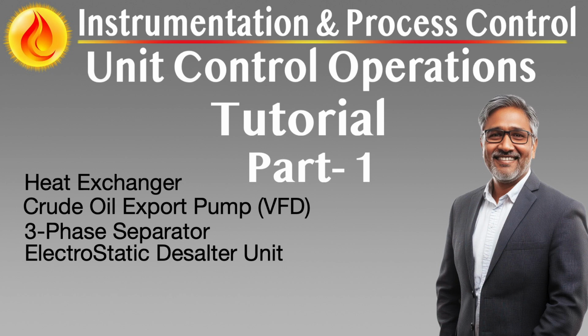From a safety and reliability standpoint, electrostatic field protection has matured. Spark detection sensors, field harmonics monitors, and predictive insulation diagnostics alert operators before dielectric breakdown occurs. Automatic field shutdown and restart sequences are integrated with brine level alarms, pressure reliefs, and water carryover sensors. In advanced systems, digital twins simulate the desalter's electrical field behavior and flow patterns, enabling virtual testing of field configurations and preemptive mitigation of upset conditions.